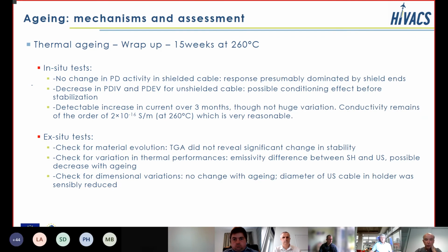So, a wrap up about these experiments. We didn't detect any change in the PD activity in a shielded cable, and we believe that we are probably testing mostly the shield ends of the cables in this condition. For the unshielded cables, there was a detectable decrease in the inception voltage before stabilization. For the current measurements, it was relatively stable over 3 months. We had a detectable increase in conductivity, but it is still a very, very low conductivity for the materials. For the TGA test, there was no sign of evolution of the PTFE material.